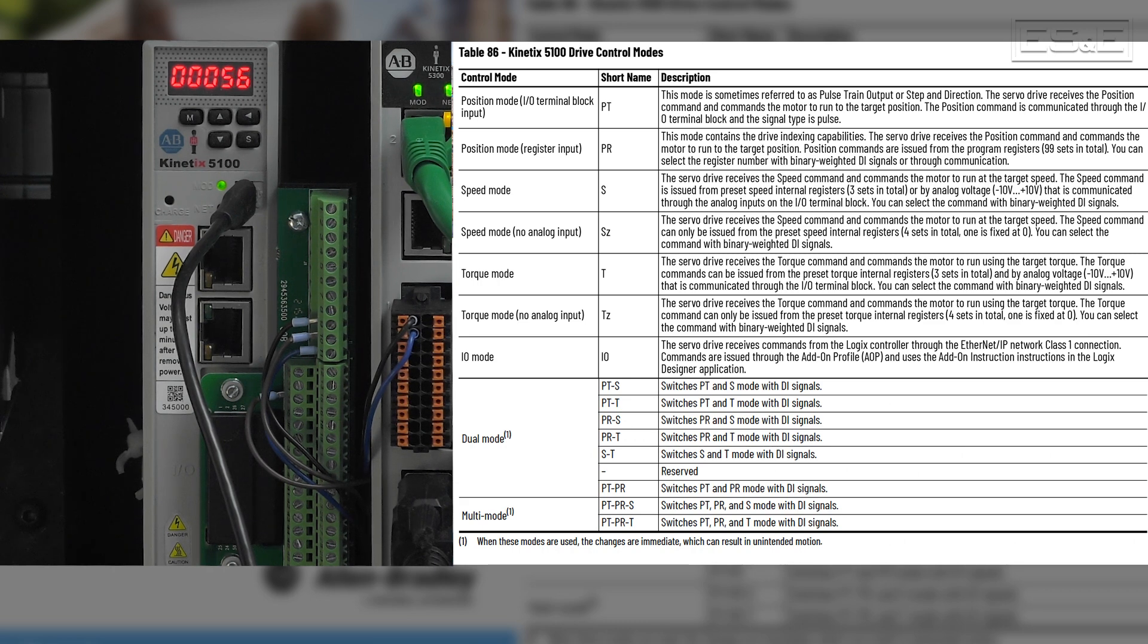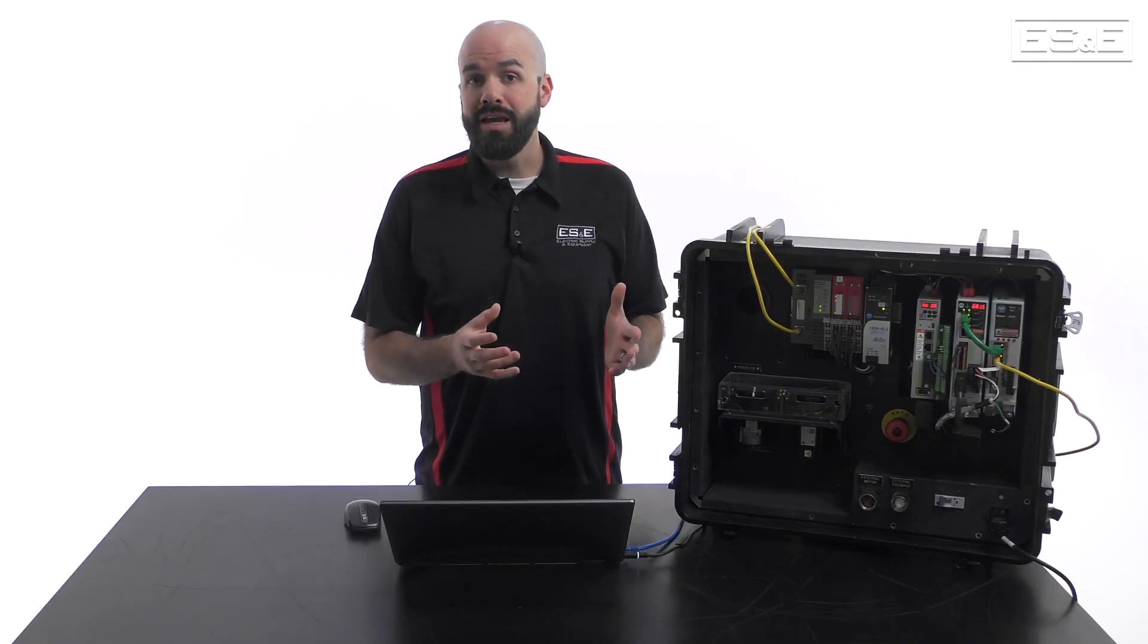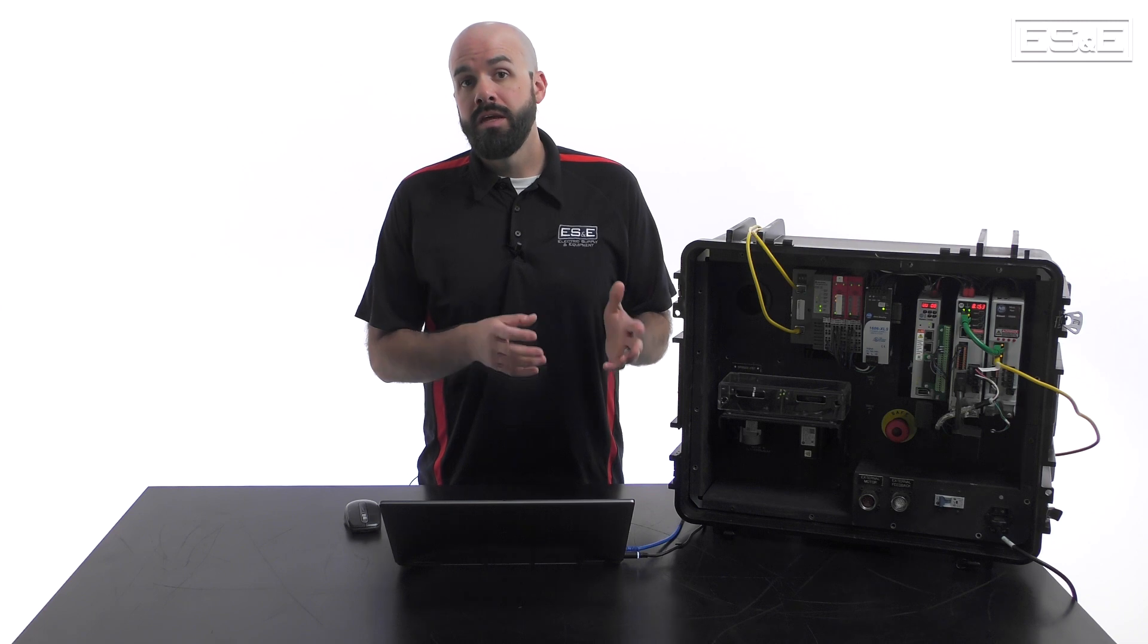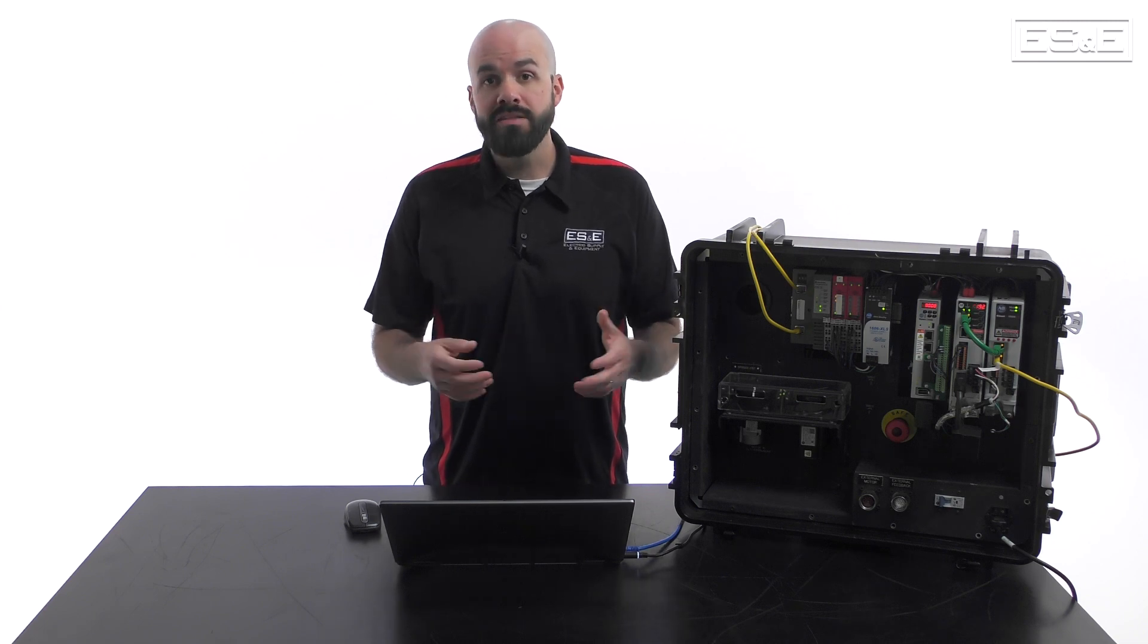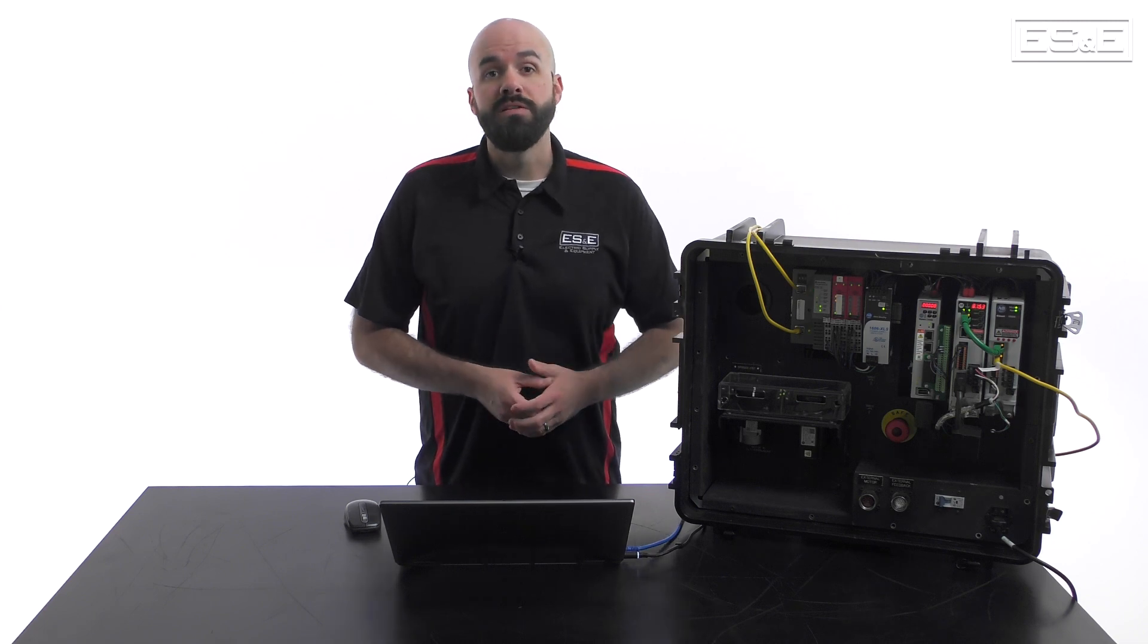I am going to walk through the process of setting up the Kinetix 5100 in PR mode, which is position command with internal register input mode. This mode will allow you to create index moves internal to the drive and execute them with digital inputs.